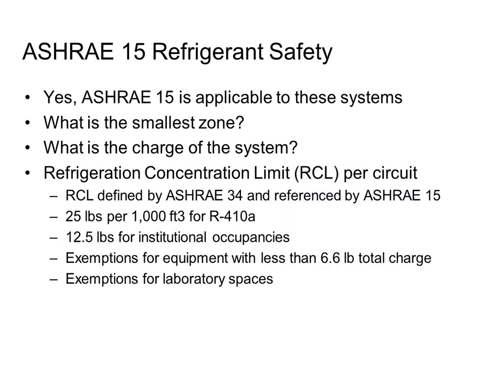Let's look at Andrew's question. Andrew's asking about 100 cubic feet. Is that only for occupied spaces? Does that include unoccupied spaces like mechanical rooms? Yes, it does include unoccupied spaces, which is why when we have chillers in mechanical rooms, it typically kicks in the rules where we have to have refrigerant monitoring systems.